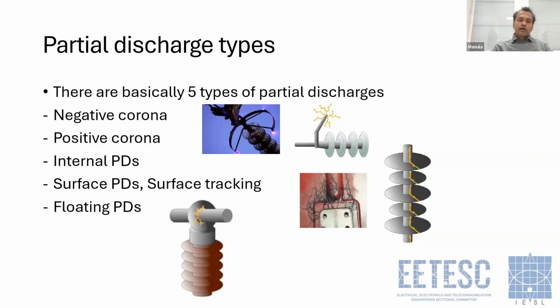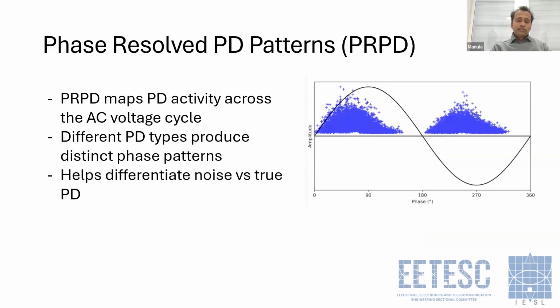Okay, so now we know there are different types of partial discharges, and let's see how we can identify or classify these types of partial discharges. Depending on the type of partial discharge, the amount of discharge would depend on the phase, so we can correlate that to the AC waveform. If you take an AC waveform, whether it is 50 Hertz or 60 Hertz, it would have a positive half cycle and a negative half cycle. So we can correlate the occurrence of partial discharge to this waveform, and we can have these kinds of clusters. These clusters are called PRPD patterns, or phase resolved partial discharge patterns.